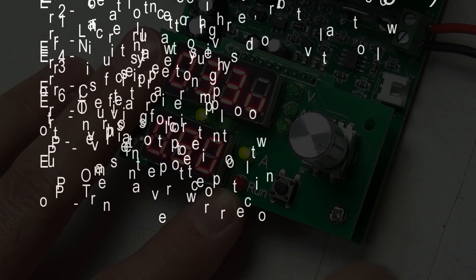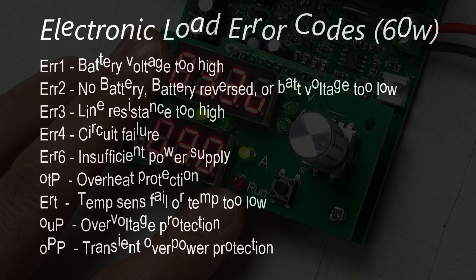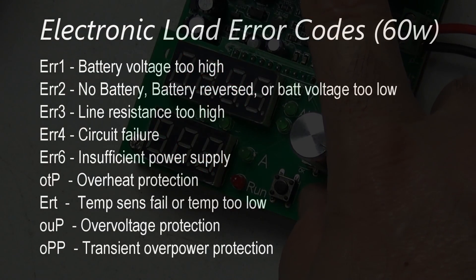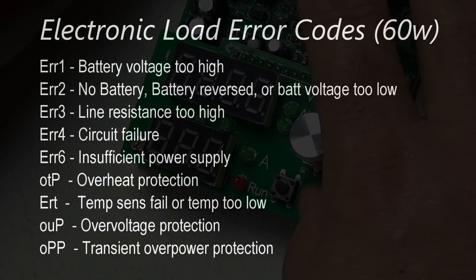So just while we're on the error codes, you've probably seen one flash up on the screen there already. Error one is battery voltage too high. Error two is no battery, battery reversed, or battery voltage too low.